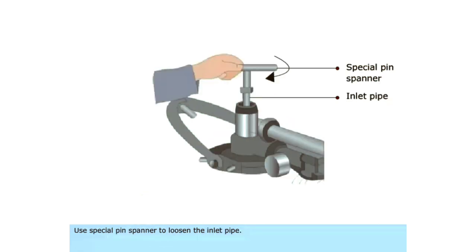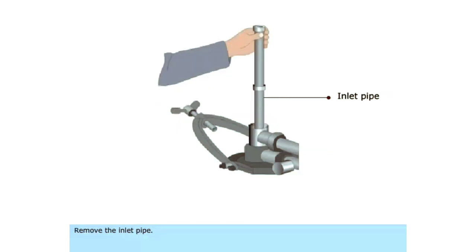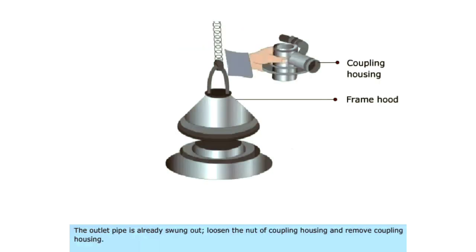Use special pin spanner to loosen the inlet pipe. Remove the inlet pipe. The outlet pipe is already swung out. Loosen the nut of coupling housing and remove coupling housing.